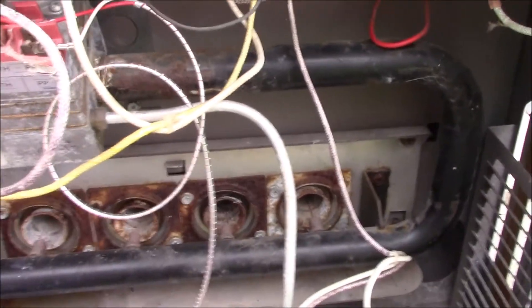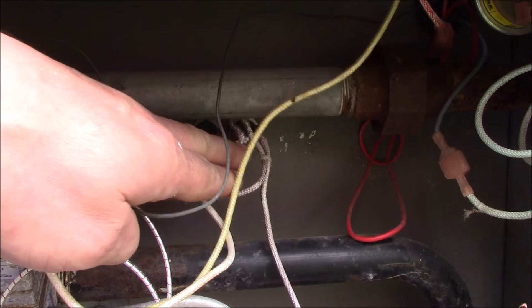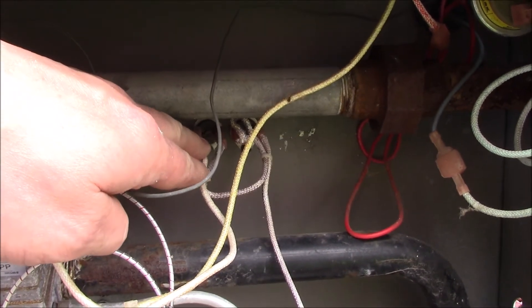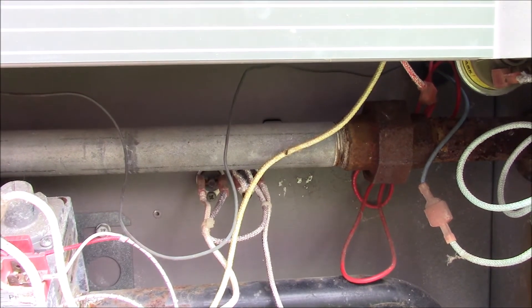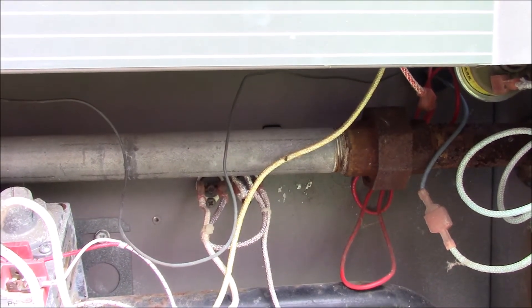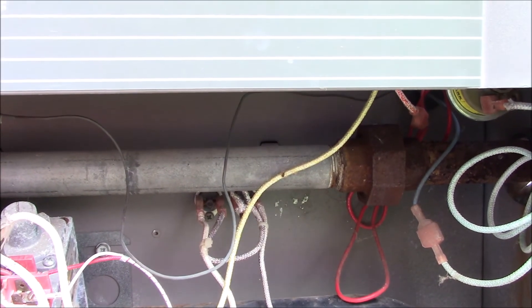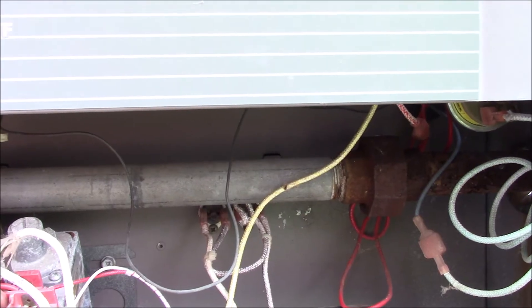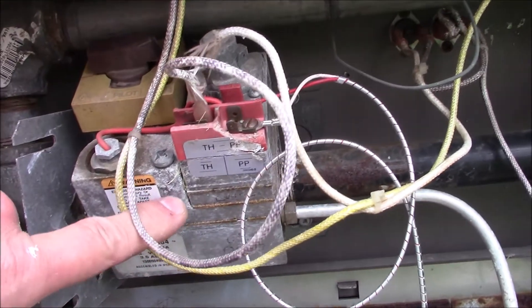Down here I'm going to check continuity on these two safety devices. If it gets too hot, it's a thermal break and it's self-resetting, but there are occasions where they stick in the open position. Both of those have to have continuity running through them before this gas valve will open up with the half-volt signal.